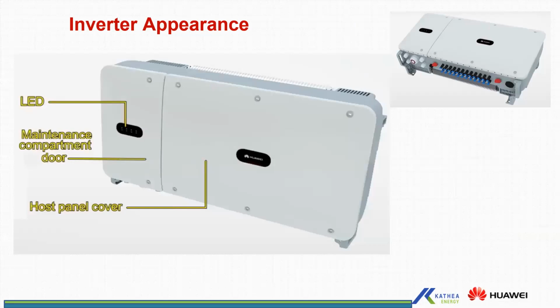The HUAWEI inverters are touch free. In that design, they try to remove all the quick-wear parts, that is buttons, screens, fuses, because usually after 3-5 years those need to be replaced, and that affects inverter availability and efficiency. So our inverters are touch free. There is no button, there is nothing. The only thing there is a DC switch at the bottom of the inverter. For all your settings and checking inverter status, everything is done through the Fusion Solar app.